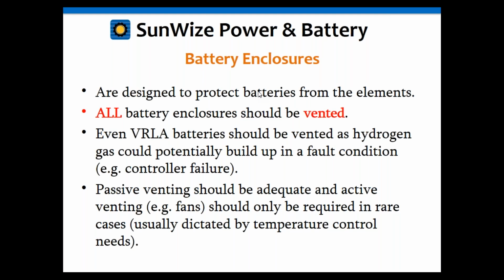I didn't put the specific IEEE document up here because there are different documents for standalone PV batteries versus hybrid batteries versus UPS type batteries. They have like 4 or 5 different standards for batteries. I didn't want to put them all up here because there are different ones depending upon the application you're using the batteries with, but they all state the same thing: batteries should be vented to prevent any buildup of hydrogen gas that could occur in a potential fault situation.